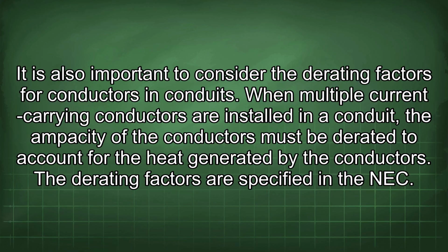It is also important to consider the derating factors for conductors in conduits. When multiple current-carrying conductors are installed in a conduit, the ampacity of the conductors must be derated to account for the heat generated by the conductors. The derating factors are specified in the NEC.